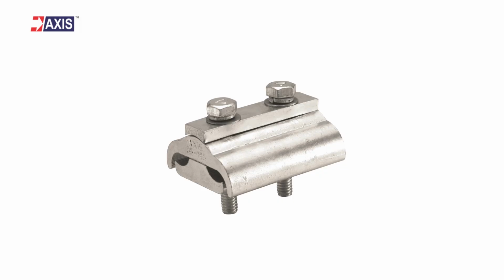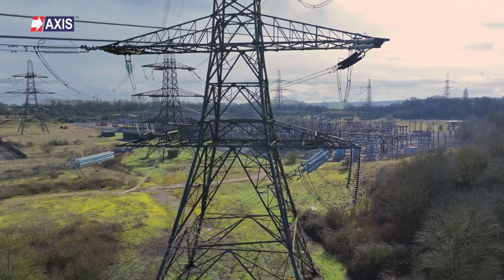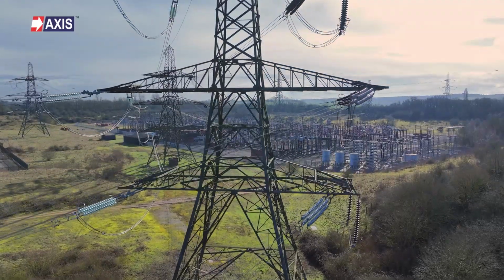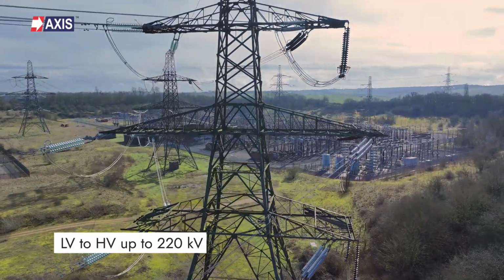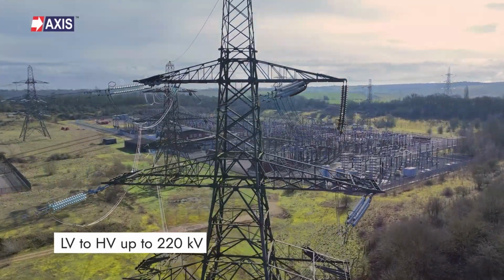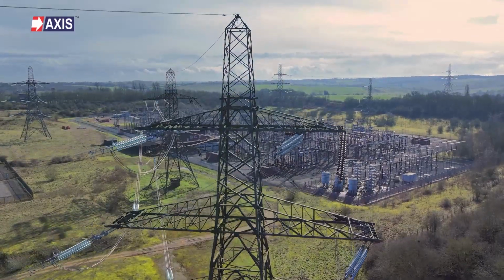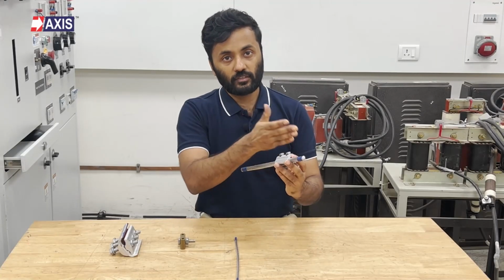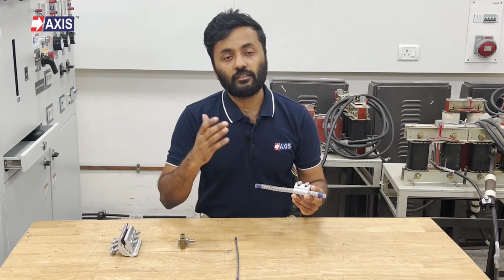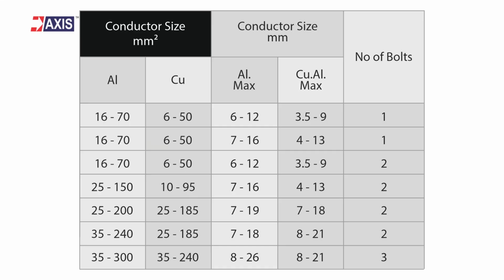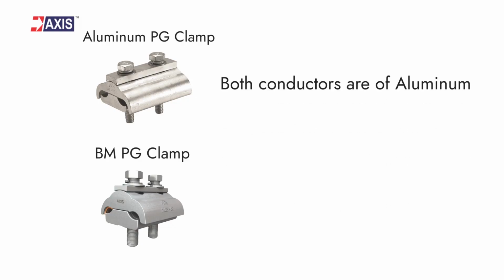Starting with the Aluminium PG clamp. This PG clamp is mostly used on aluminium power conductors for power distribution and transmission, ranging from low to high voltage up to 220 kV applications, depending upon the designs and specifications. They are designed to connect two conductors in parallel to accept a tap connection. There are different types available in the market like single, double and 3-bolt clamps. The types vary depending on the size and current carrying capacity of the conductor. An aluminium PG clamp is used when both conductors are made out of aluminium.